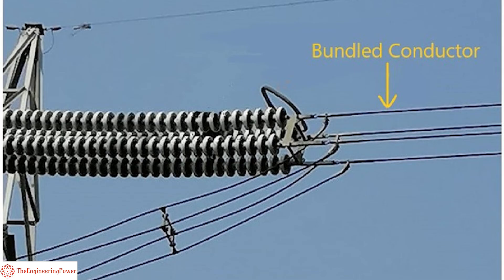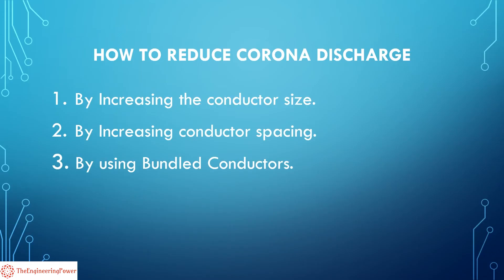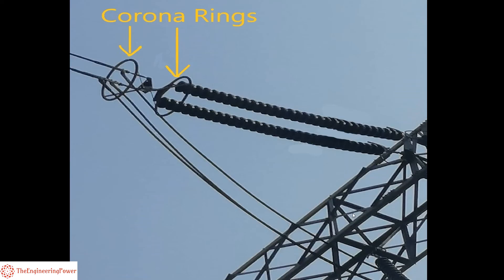The next method is the use of bundled conductors. With bundled conductors, the effective diameter of the conductor is increased, resulting in low corona loss. That is one of the main reasons behind the use of bundle conductors on high voltage transmission lines.